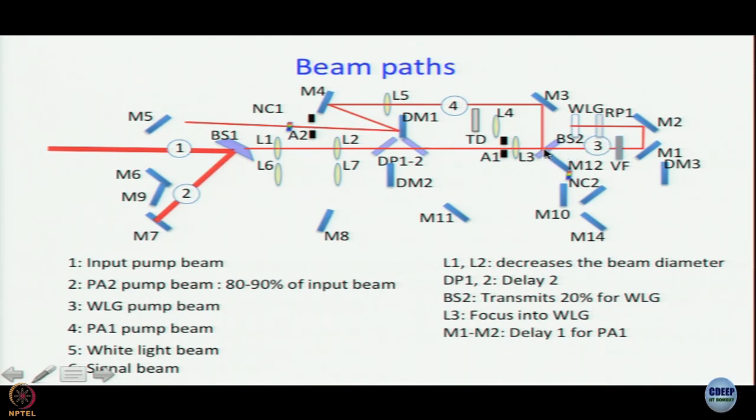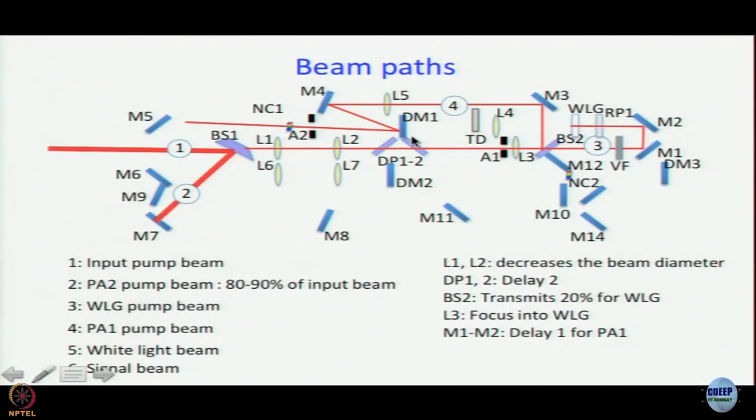What we said is the 80 percent of the light that is reflected by BS2 hits M3, that is path 4 which is PA1 pump beam, the preamplifier pump beam, and remember this is a focusing beam. So it is collected by L5 which serves to collimate it, then the collimated beam hits M4 then dichroic mirror 1. As we discussed in the previous module, this dichroic mirror is essentially a short pass filter, so it reflects the 800 nanometer light. This 800 nanometer light goes through an aperture A2 and this nonlinear crystal NC1, and then it is dumped.